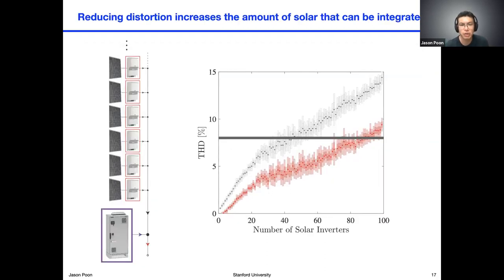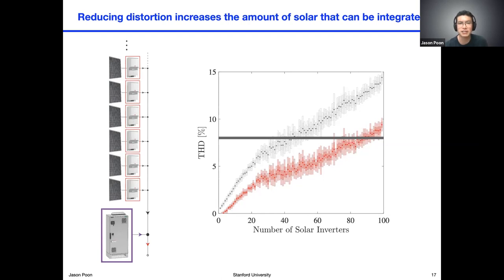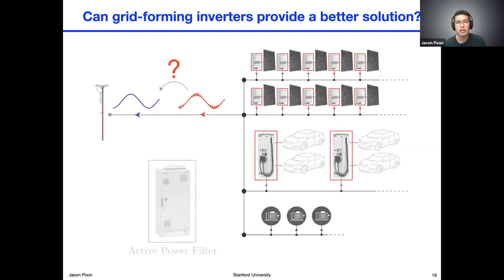It does work, though. If we add in this active power filter to our simulation, the distortion has been reduced quite significantly — reduced to the point where we don't cross the 8% limit until about 80 or so inverters. So we've effectively doubled the amount of solar that we can integrate into this example network with the introduction of this active power filter.